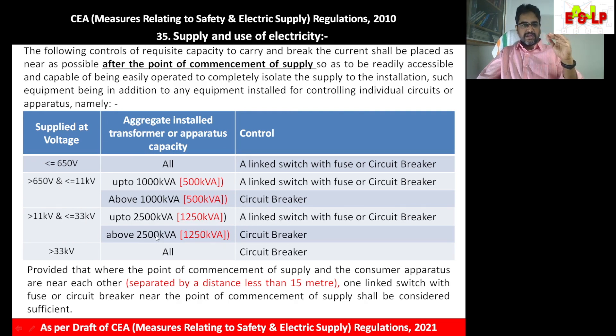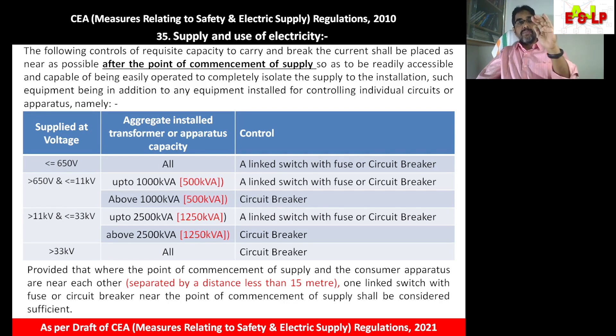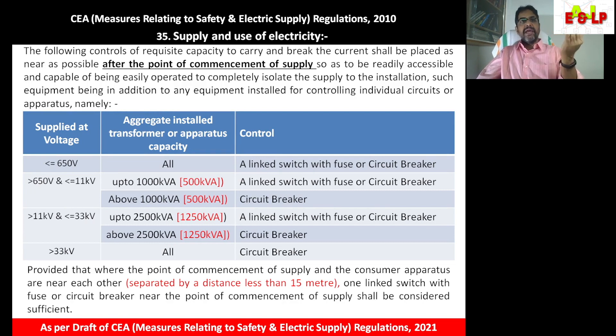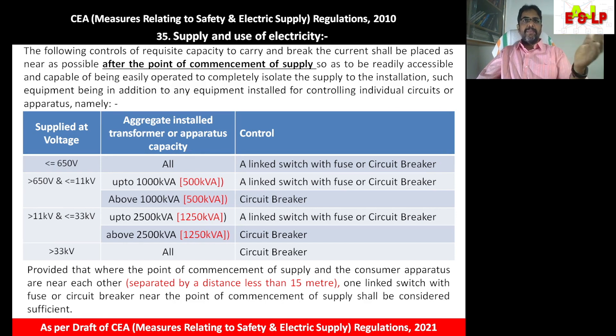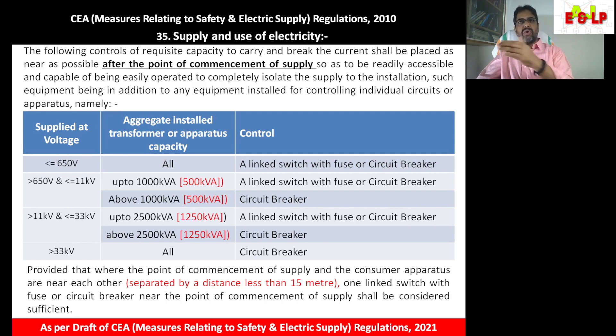There is an additional condition: the switchgear must be provided as near as possible to the point of commencement of supply. However, if there is a main switchboard or distribution board near the point of commencement of supply, there is no need to provide an additional switching gear or circuit breaker — it is not required.